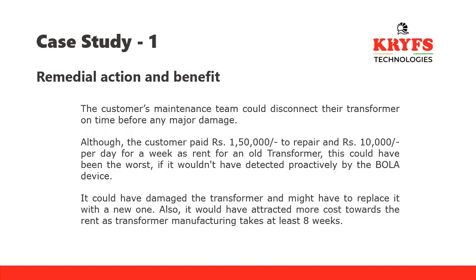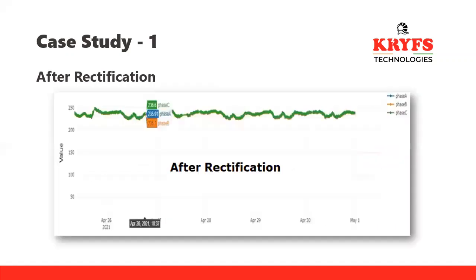And this could have been worse if it had not been detected proactively by our BOLA device. It could have damaged the transformer more, and they might even have had to replace it with a new one. It would also have attracted more cost toward the rental of a transformer, and manufacturing a new transformer may take around 8 weeks. So because of this proactive monitoring, they have reduced the operational cost and repairing cost of the transformer.